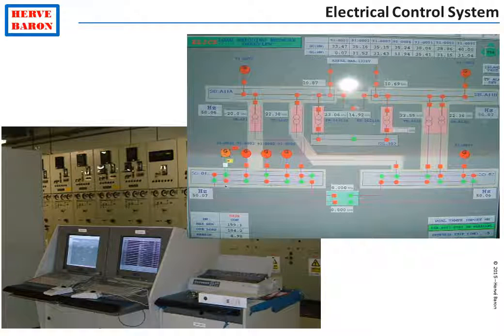A load-shedding system is implemented so that in case of loss of main power generators, the limited essential power available from the emergency generators is fed to essential consumers only. This load-shedding, together with other monitoring and control functions of the electrical system, is performed in the electrical control system, also called the Power Distribution Control System (PDCS). Now, let's look at the drawings produced to install all this equipment at site.